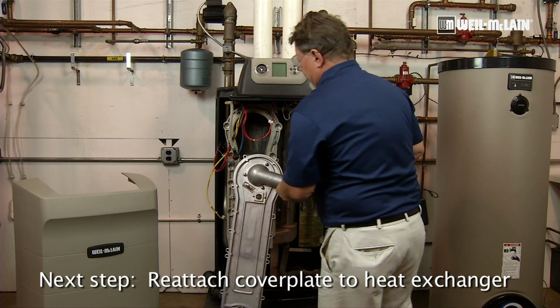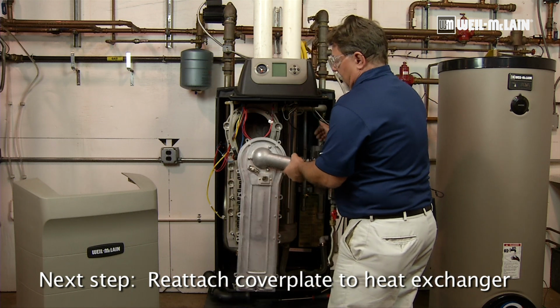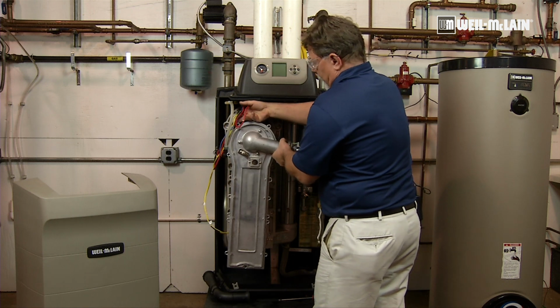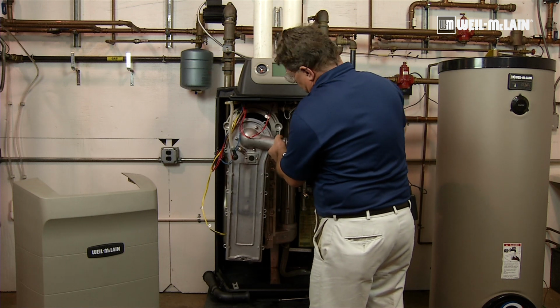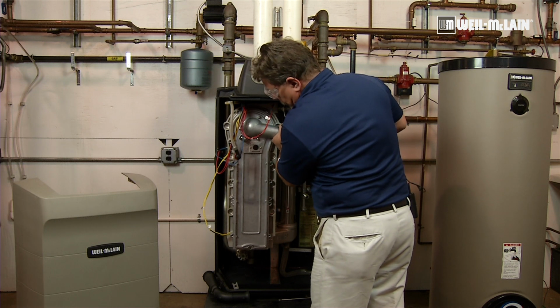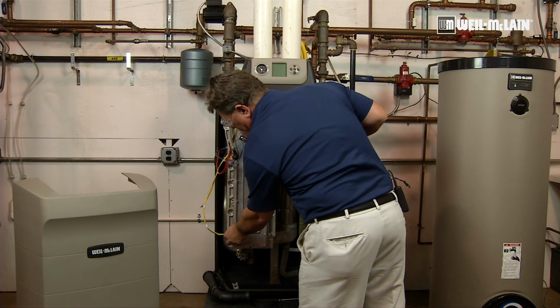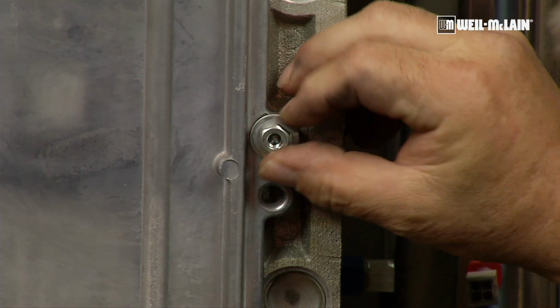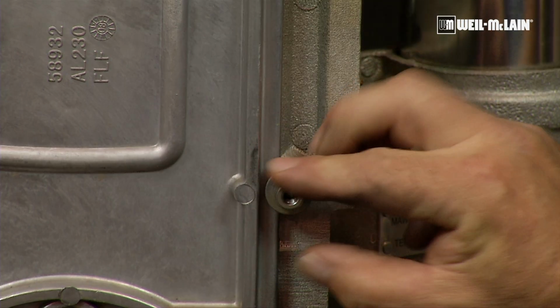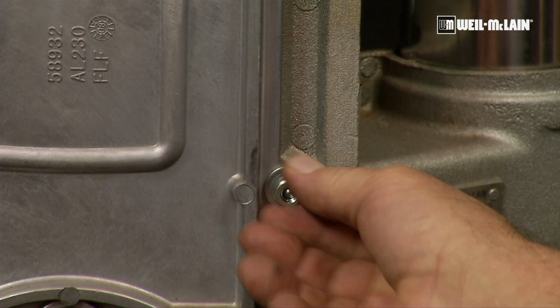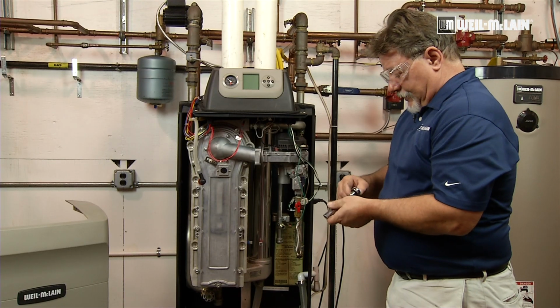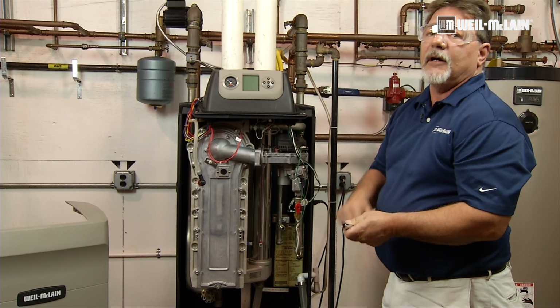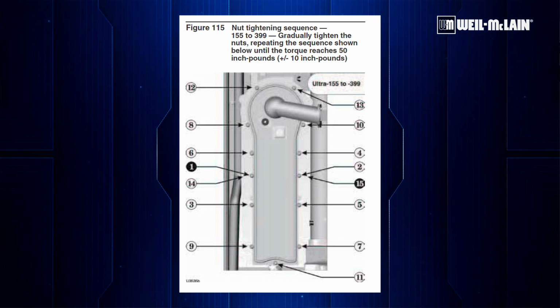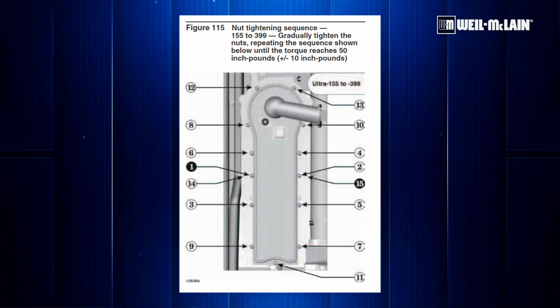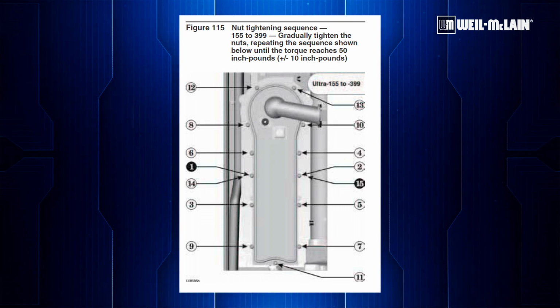So what we're going to do is simply reassemble, again, the components, and we're gently going to put the cover plate back on the boiler. And once that guy's on there, then we can go ahead and put all the nuts back on. And once we have all the nuts on finger tight, we're going to take our socket wrench and we're going to tighten them up just hand tight only. And we're going to actually start in the center and work our way radially outward.